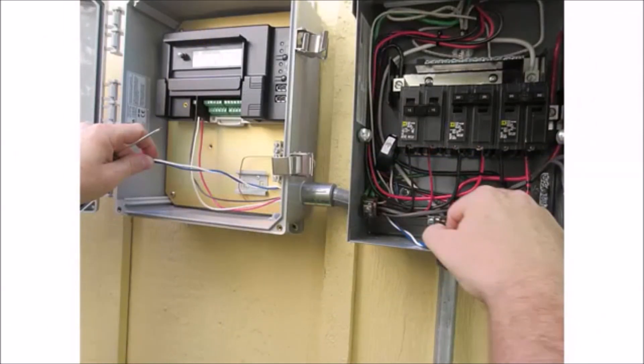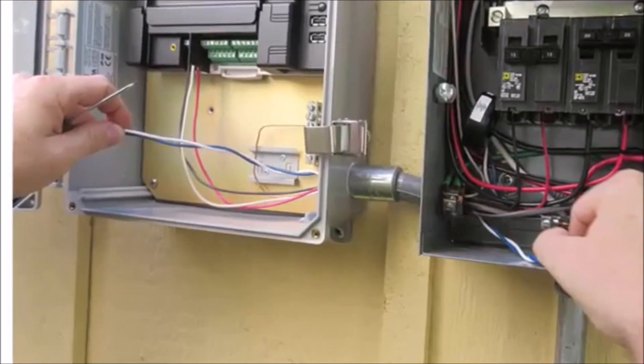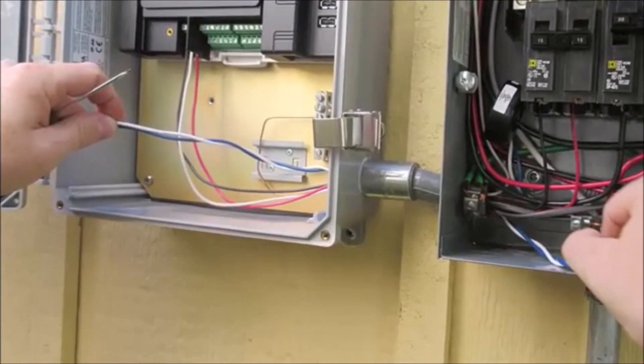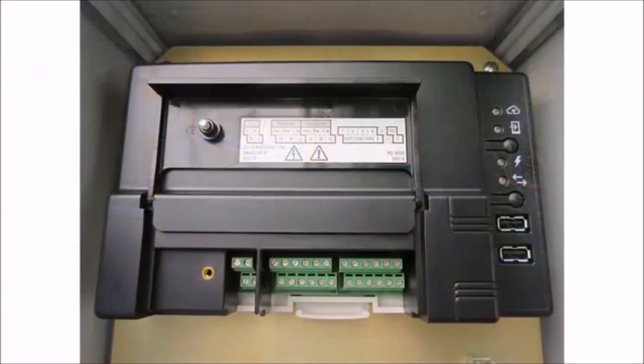Run CT wires through the conduit to the Envoy-S. Because the CT wire voltage is rated for 600 volts, you can use the same conduit as the power conductors and pull all of the wires through the conduit at the same time. Open the terminal block door on the Envoy-S.